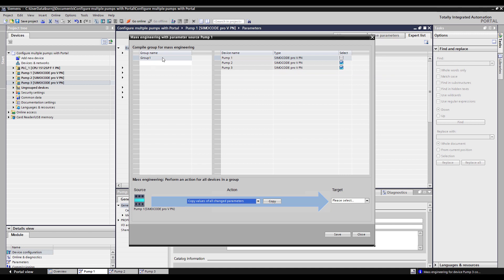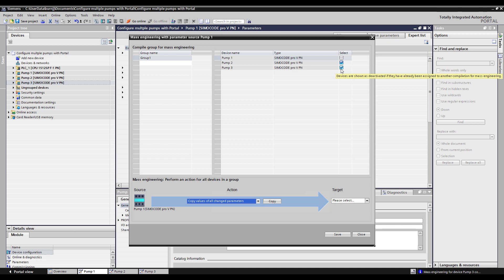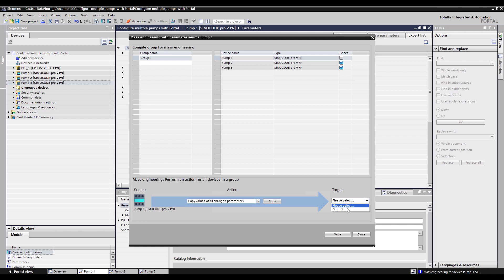Group one has now been assigned to have pumps two and pump three in it based on these checkboxes. So the target becomes group one. This configuration takes the parameters that have been changed in pump one and transfers them to group one which consists of pump two and pump three. So when I click copy, that change has now just been made.